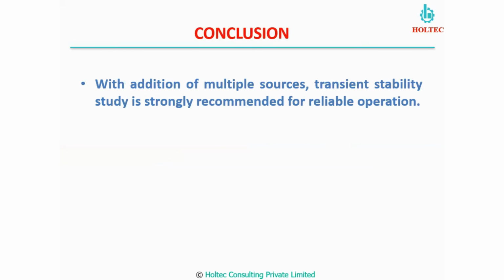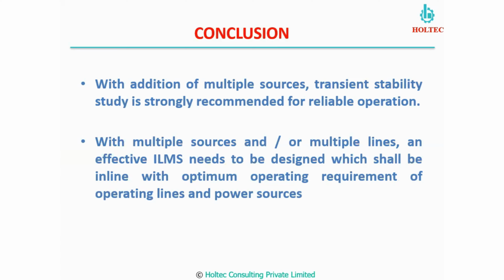With the addition of multiple sources, transient stability is strongly recommended for reliable operation, because we know the fault clearing time and we set our relays below that fault clearing time and ensure the transient stability. And if we have multiple sources or multiple lines, an effective ILMS needs to be designed which shall be in line with our optimum operating requirement and operating power lines and power sources. So for multiple sources and multiple lines, we should design an ILMS system to handle this complex power distribution situation.